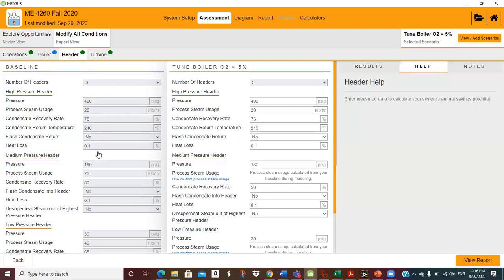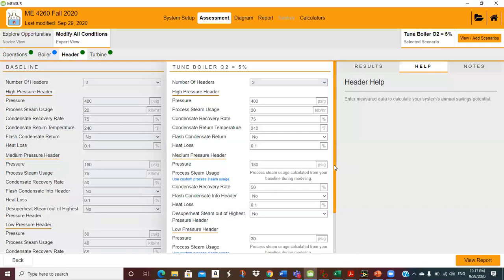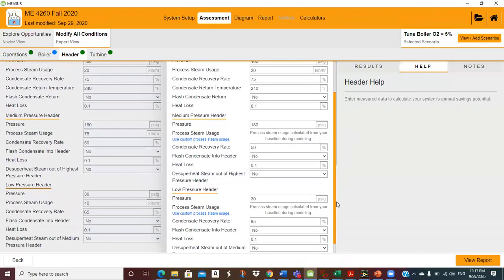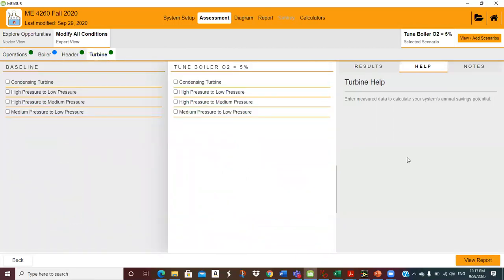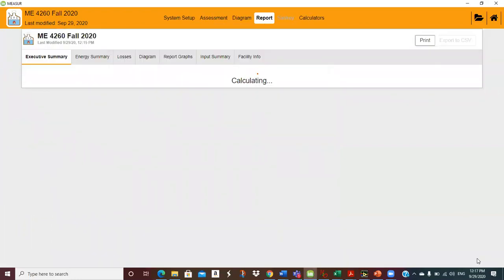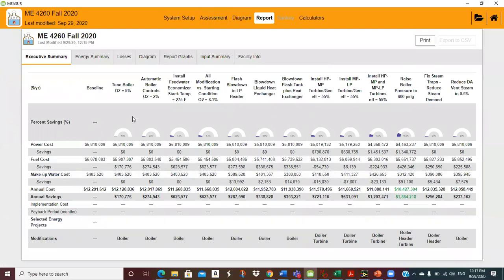We're not recovering any flash steam or heat loss — I didn't modify those numbers. Medium pressure is 180, 75,000 pounds an hour, 50% condensate return — all that. I think this all looks basically correct. The numbers should be the same on this side because all I want this to be is a change in boiler efficiency, and I don't have any turbines. So if I look at the report — that's tuning the boiler — I'm getting about 171,000 on fuel.